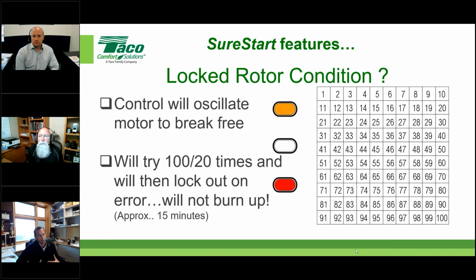Yep. And when you say that this circulator won't, that it'll recognize these situations and lock itself out and allow you to resolve the issue and then put it back into service, that gets contractors' attention probably more than anything, when they realize they don't have to have a whole bunch of 007 cartridges on the shelf. They start using ECMs and they go out, resolve the issue and put those circulators back into service. So yeah, I appreciate that, Chris. That's good stuff.